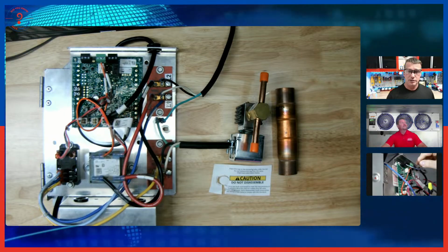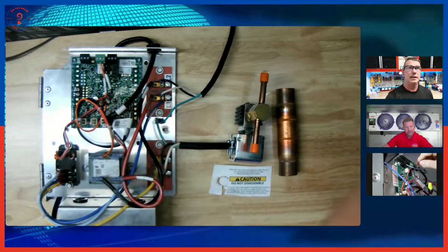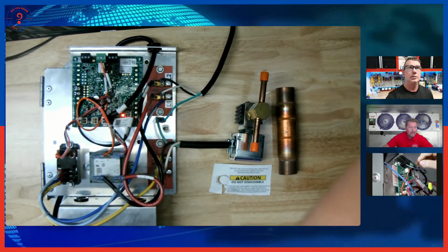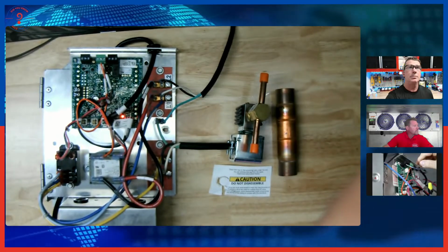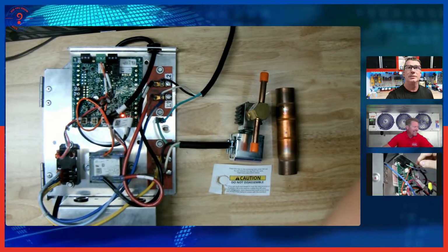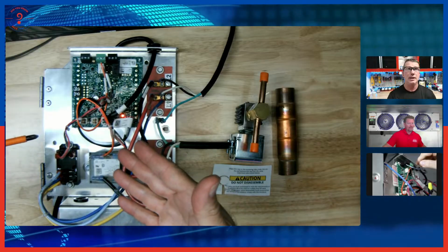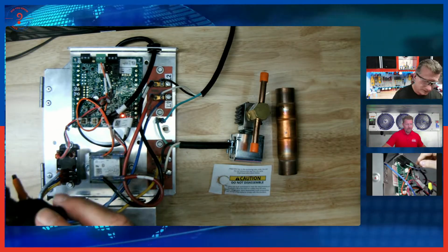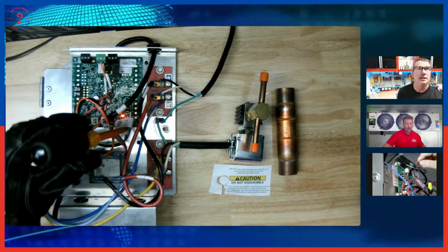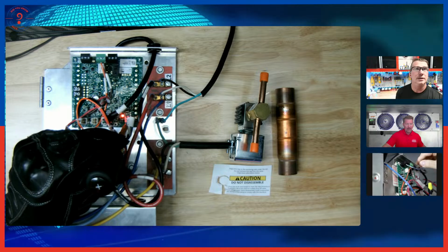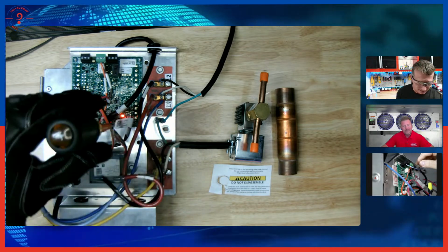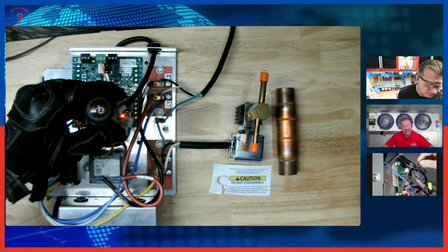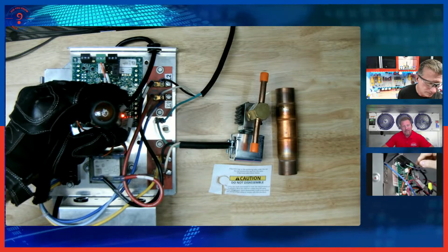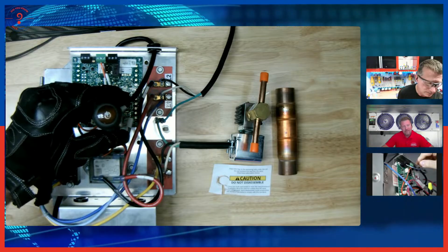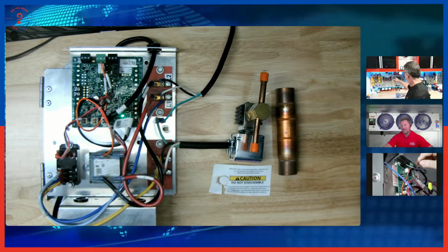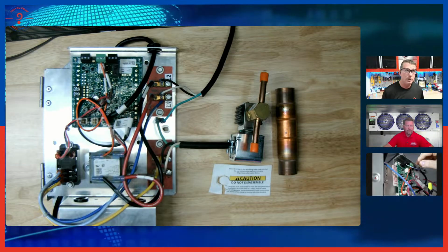All right. Very good. So let's talk about the location of that, and I'll see if I can clean that up just a little bit more. I love this manual camera, but the depth of it is not always the best. All right. So I'm going to need to actually do a reset on this control board. Your micro switch is probably going to be hidden by that white tab. Yeah. So right there by my LED. So I will hold in that micro switch. Yep. Press and hold that. There you go. Look at that. Very, very good thing to point out. So we are back in operation.